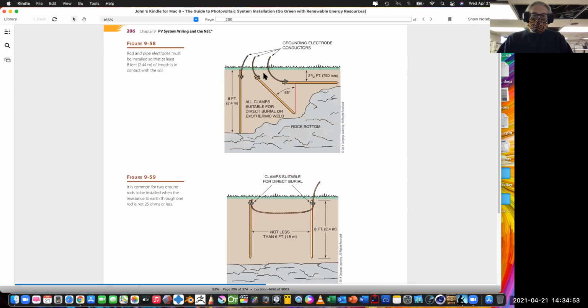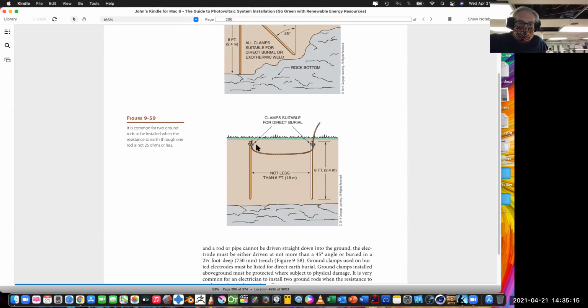Now in this case, they're showing this underground. That's not what you do usually. You can, and that's fine, but that's typically not what you're going to do because you don't connect and disconnect things underground like this. So this would be up out of the earth just a little bit with this little clamp on there that we looked at. Now you can also put multiple grounds in.